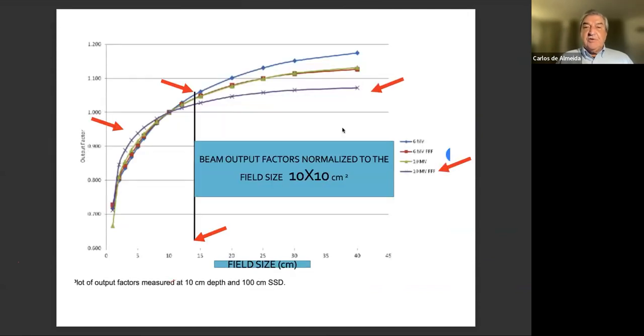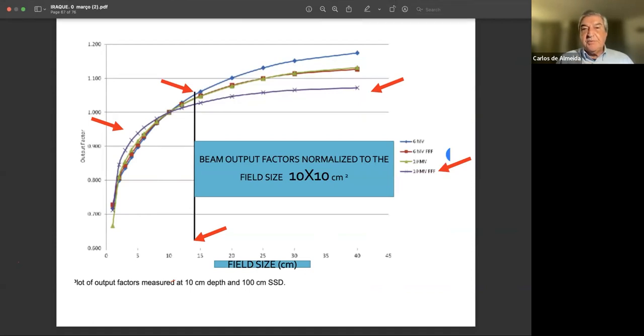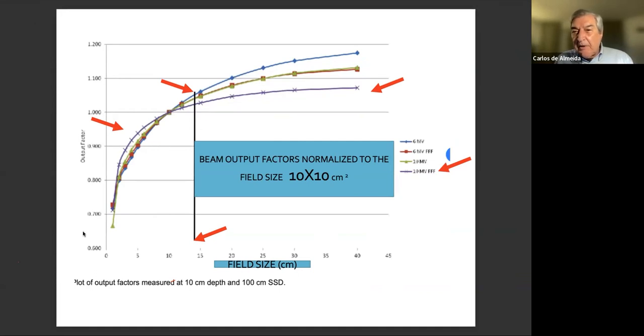Also, when you measure the output factors, this is interesting because you see here a very typical one. But this is good to see because, for instance, this blue one here is for the 6 MV, but this one here is for the flattening filter-free photons, which coincides with the 10 MV beam. And this one here is for the 10 MV flattening filter-free beam. Also, on the lower end, on the smaller field sizes, the shape changes a little bit, so you must be careful when you measure those output factors, when you normalize to the 10 by 10 field size, which is the way it's done. If you're measuring with a physical flattening filter, or if you're measuring with a flattening filter-free beam, okay? You have to be careful with that. Next one.